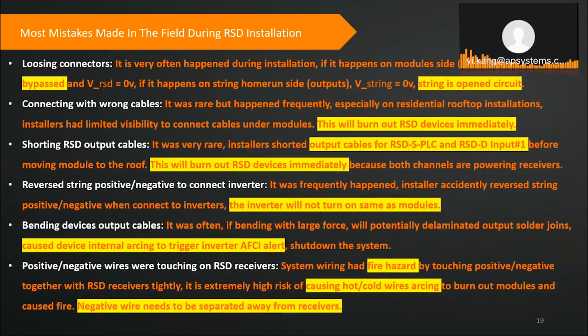And I would like to point out one of the major advantages here. I don't know if he's getting into it, but the number of failures of such a device is very low because there is a very limited amount of technology inside. It's a very simple device, so it is very unlikely to fail compared to an optimizer or even a microinverter, right? Which has much more going on versus this rapid shutdown device. Thank you, Dan. I will get to that part also later on.